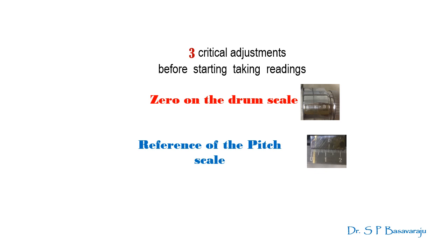The third adjustment is against what is known as the backlash error. All micrometer type TMs almost always have a backlash error. They acquire this problem gradually within a month or two after they are put to use in the lab after they arrive there as a brand new instrument. It's simply because of the wear and tear of the threads on the screw in the instrument. You should be absolutely careful about this error also. If you don't take care of all these three factors, you are likely to end up with a mess of measurements.